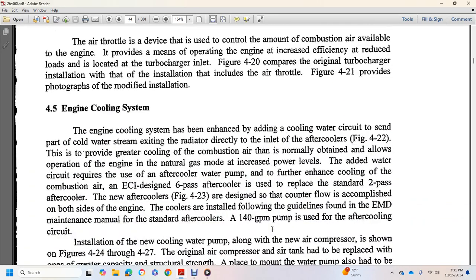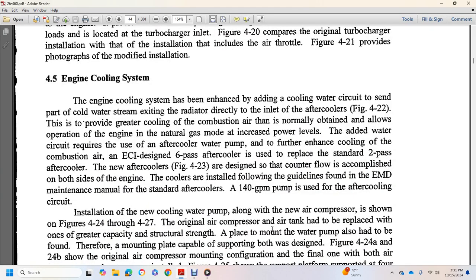Figure 4.5, engine cooling system. The engine cooling system has been enhanced by adding cooling water circuits to some of the parts of the existing cooled water stream, routed directly to the inlet of the aftercooler. Figure 4.22 provides greater cooling of the combustion air than is normally obtained, allowing operation in natural gas mode at an increased power level. The added water circuit requires an aftercooler water pump, further enhancing cooling of the combustion air, with the ECI designed 6-pass aftercooler replacing the standard 2-pass aftercooler.